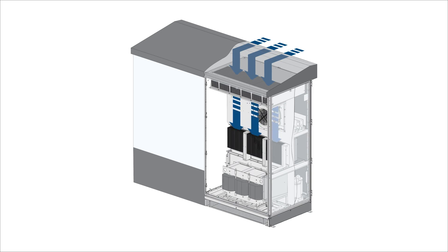A high-speed fan pulls the cool air over IGBT heat sinks and inductors. Finally, the warm air is pushed out through an opening located at the back of the inverter. Here another screen ensures that no outside particles enter.